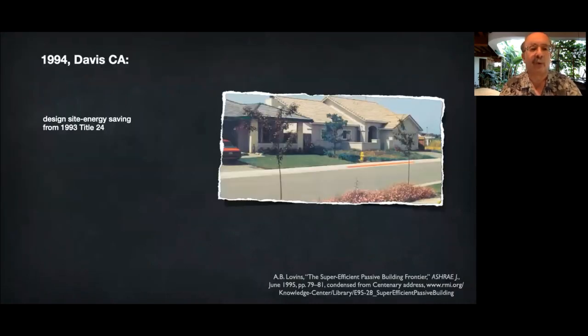Let me dive into a simple example. Twenty-six years ago, a 155-square-meter experimental house was built in central California, where a hot day reaches 40 Celsius and the maximum is 46. Yet this house achieved superior comfort with no air conditioner, and it would cost less than normal both to build and maintain if built in a mature market. First, designers improved the layout to eliminate seven meters of superfluous perimeter, put windows in the right places, and devised an oriented strand board wall that saved three-fourths of the wood, doubled insulating value, improved strength, airtightness, durability, stability, and speed of construction — and cost $2,000 less to build. Together, these improvements cut site energy use to 15% less than the then-strictest U.S. standard, saving $4,000 of construction cost.